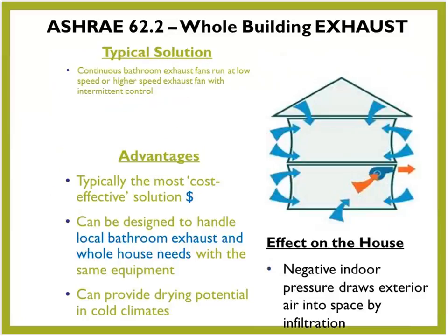Okay. All right. Again, not to contradict, but if we're hooking that HRV or ERV up to the furnace motor to distribute air throughout the house, there's going to be some long-term operating costs there running the ERV, HRV as well, where a DC motor exhaust fan might be more cost-effective. But we can have that...